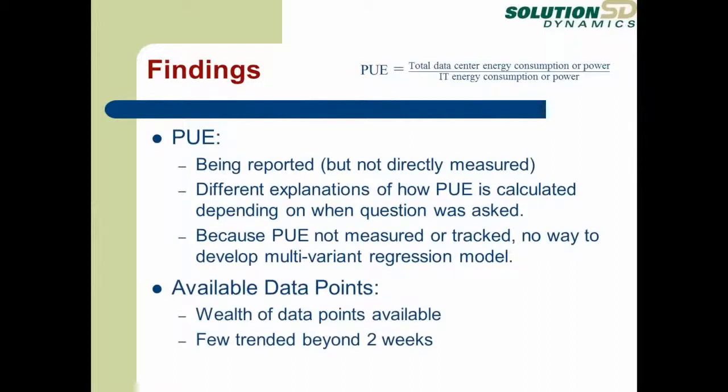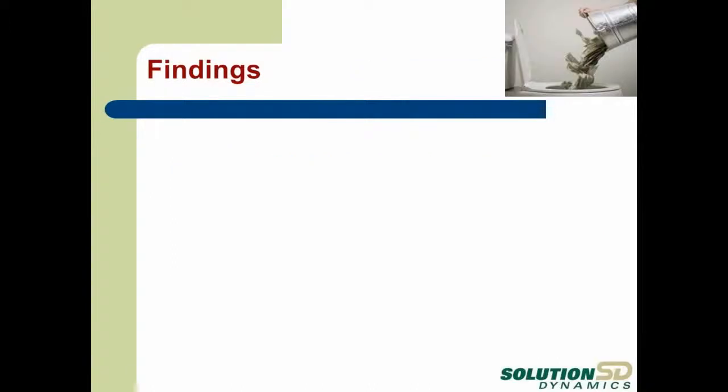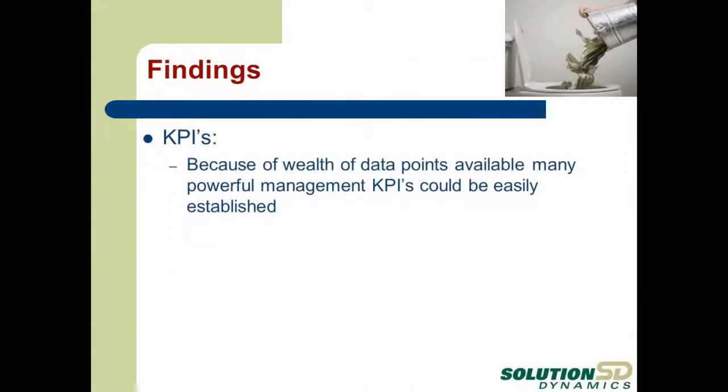After we started digging into things, we started to realize that their actual data center efficiency was probably closer to a PUE of 1.5 or 1.55, just because the methodology that we were finally able to uncover that they were using was woefully inadequate. So that was one of the findings. But as we moved through, we found lots of good opportunity.